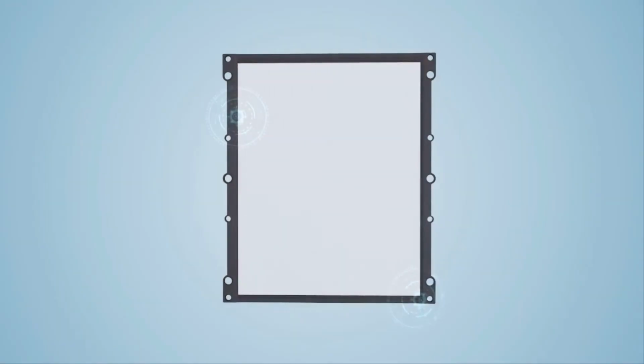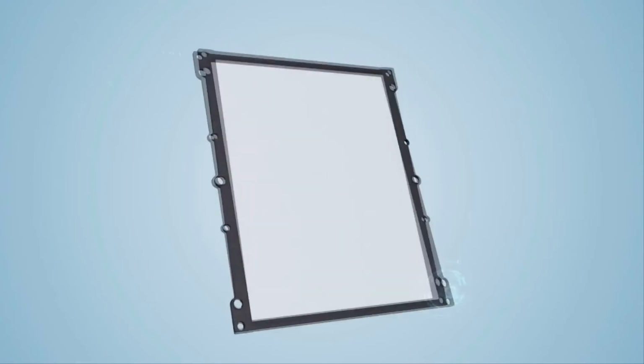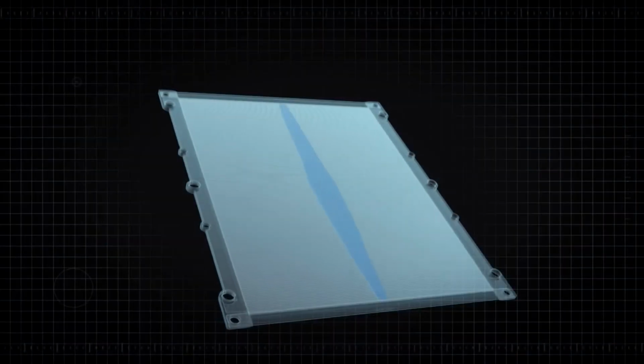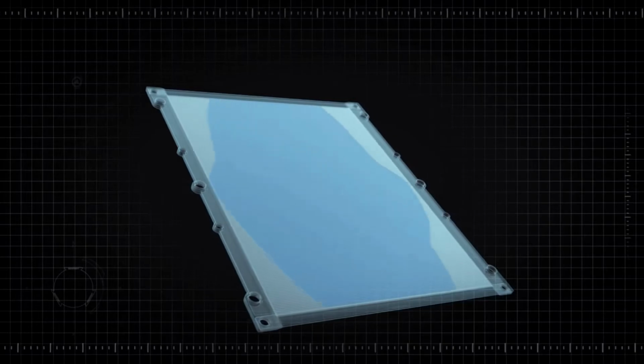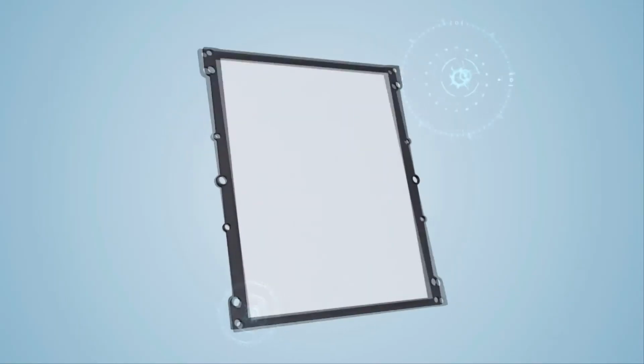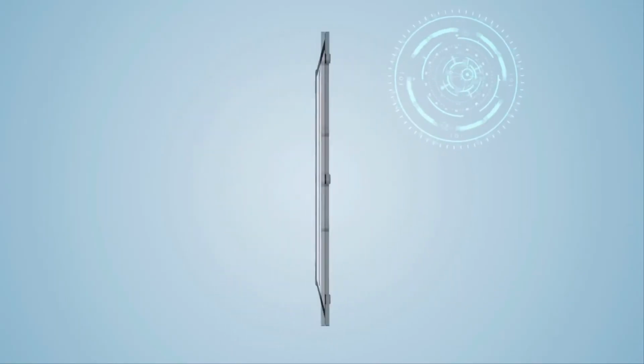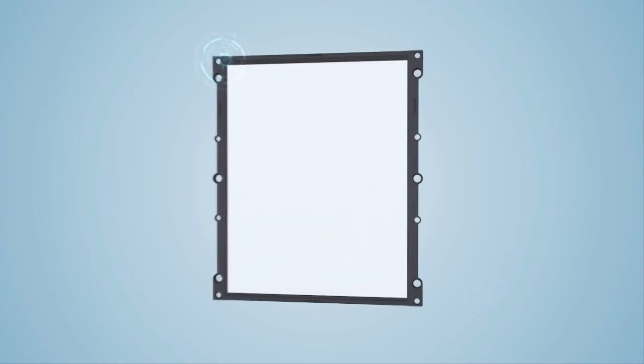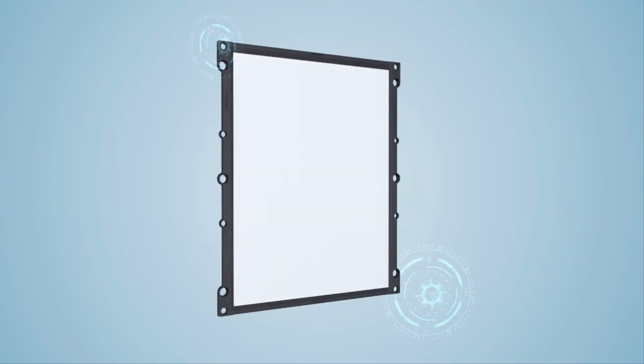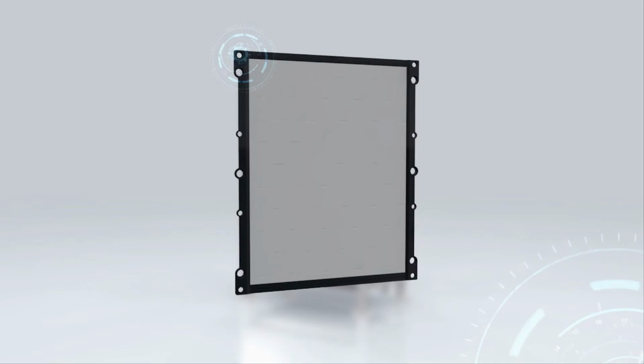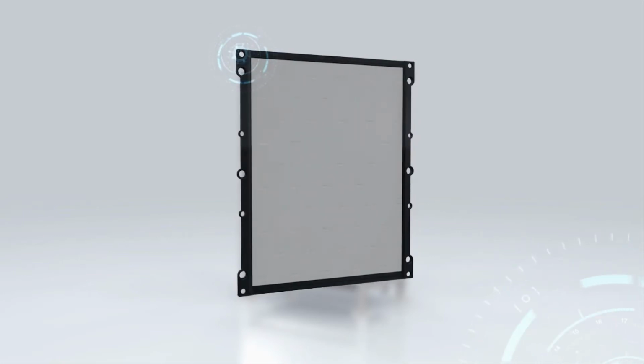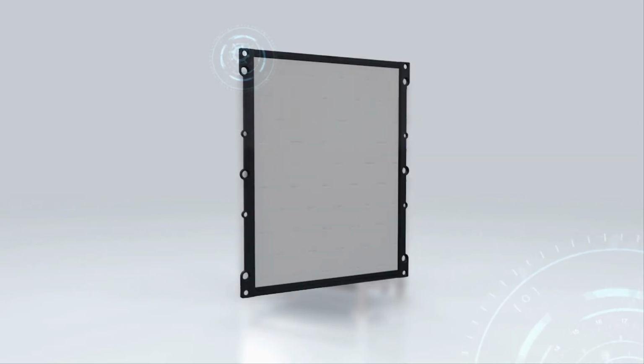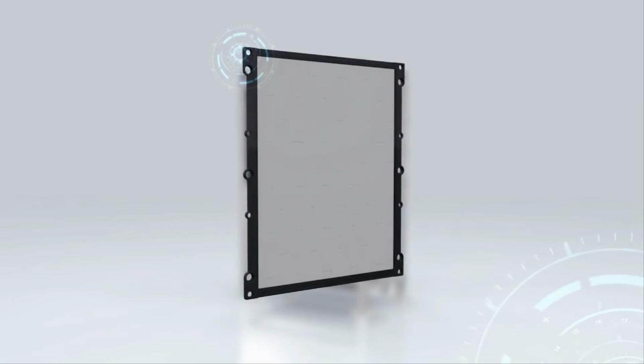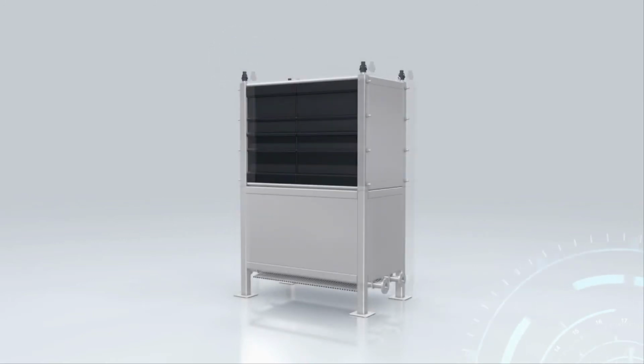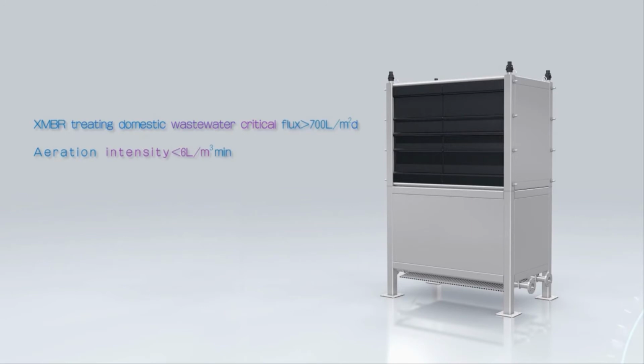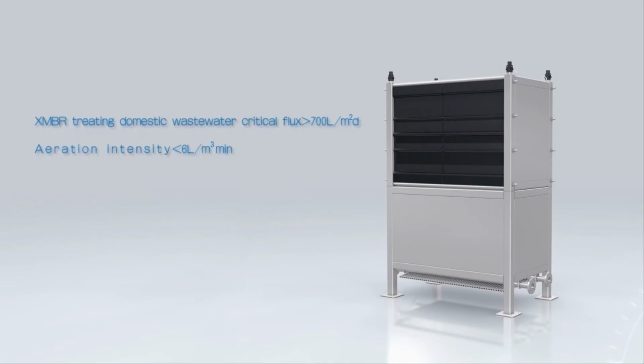By the creative design, XMBR owns a gradually enlarged effluence path and extremely lower resistance loss, working under lower transmembrane pressure. Having solved the above-mentioned difficult problems, XMBR is less likely to cause fouling on the membrane and can keep stable filtration operation. Meanwhile, because its sectional permeate flux is even, the working area of the membrane is nearly equal to its installed area. The average flux value could be taken higher, or the aeration intensity value could be taken lower.